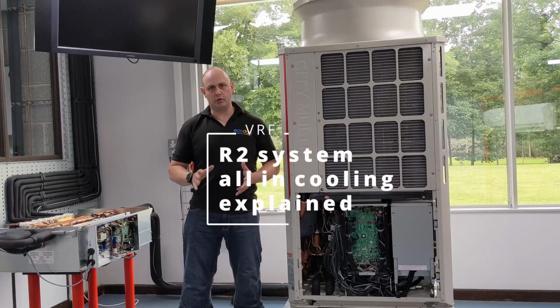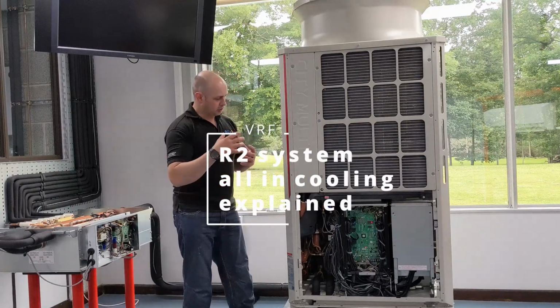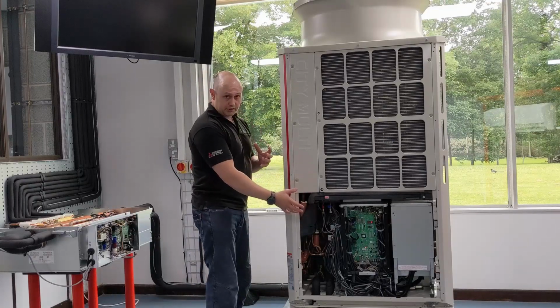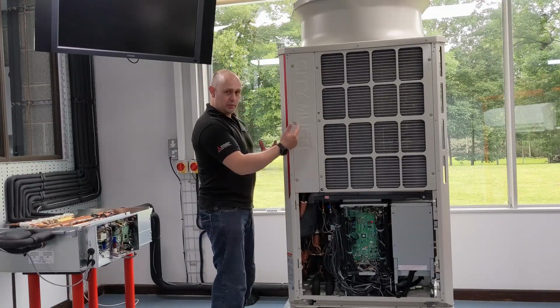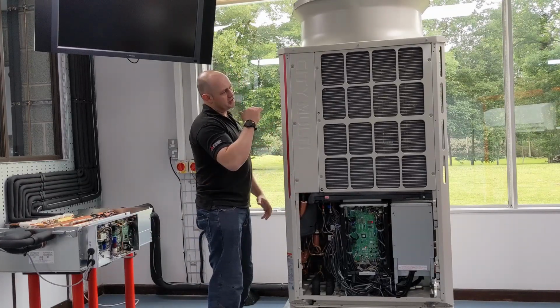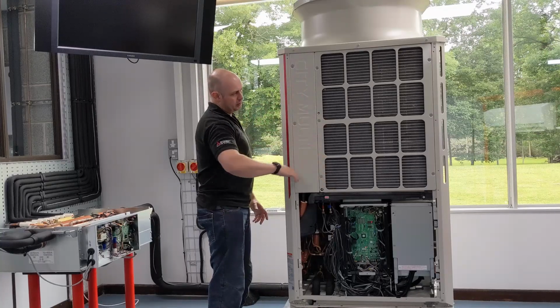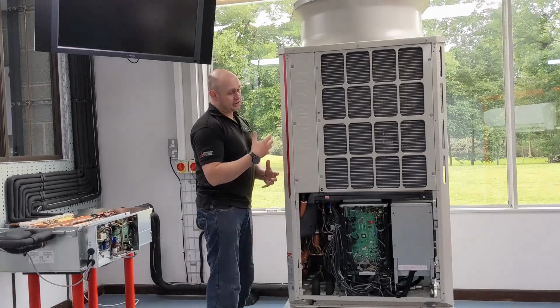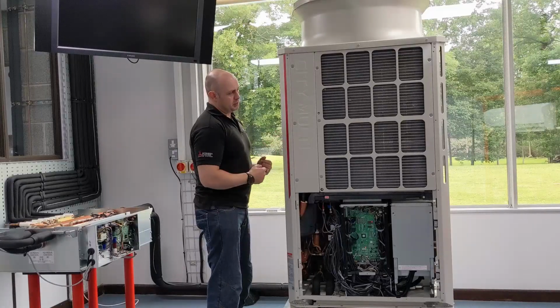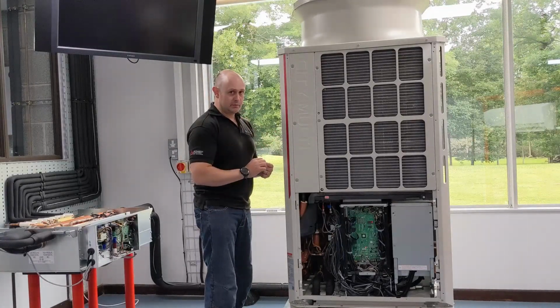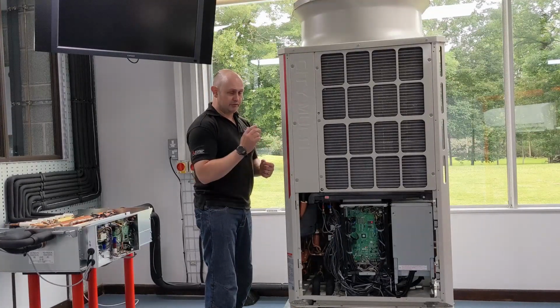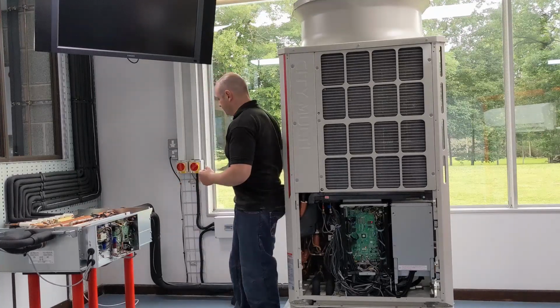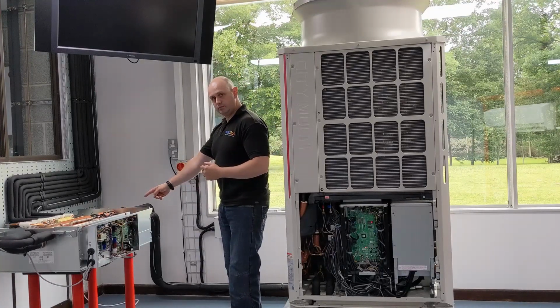VRF full cooling. So first off, we've got the refrigerant going from the compressor, passes up to a reversing valve, and then we're going to send that refrigerant through this coil, changing it from being a superheated vapor to being a liquid with a tiny bit of subcooling. And from there, we're going to send that off and into this BC box.